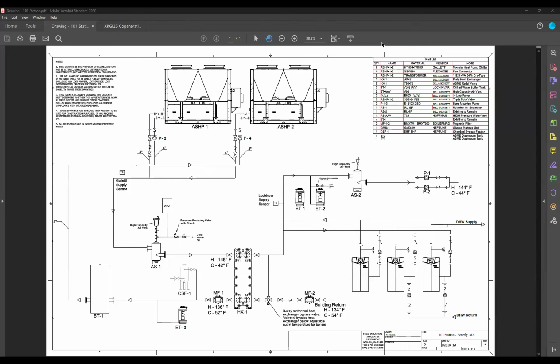Oop, wrong button. Either way, what I want to show you here is that this is a similar system. It's just not domestic anymore. Now we're looking at space heating and cooling. In this case, we had a building with a couple of existing boilers and a few chillers that had failed, which is typically the common story. If there's an existing chiller, people aren't usually just pulling it out unless it's close to its end of life. But this is an example where the boilers maybe have a couple years left and the chillers are at the end of life.